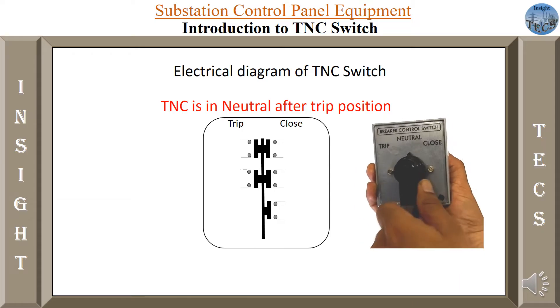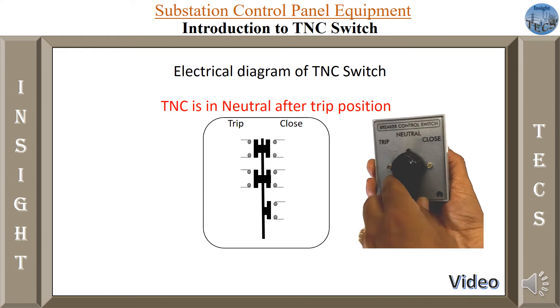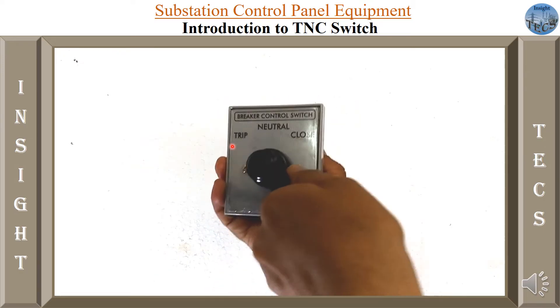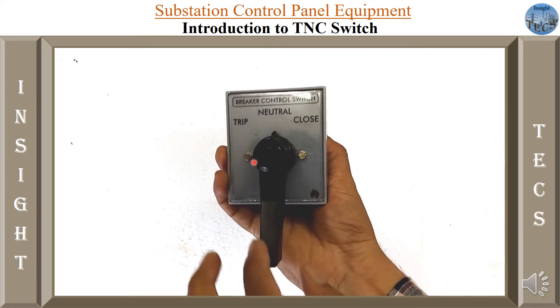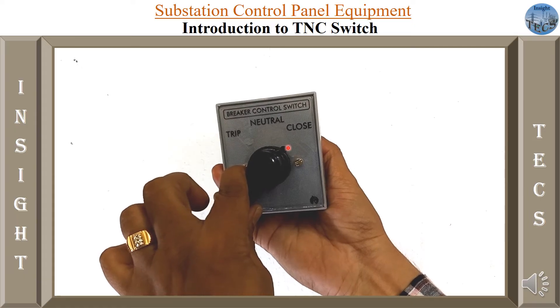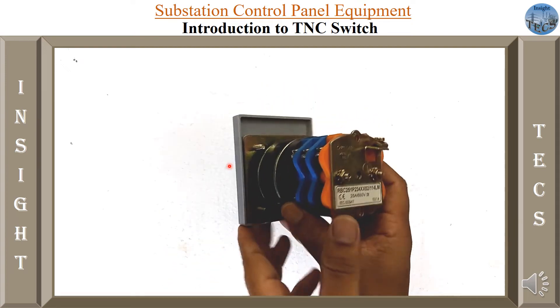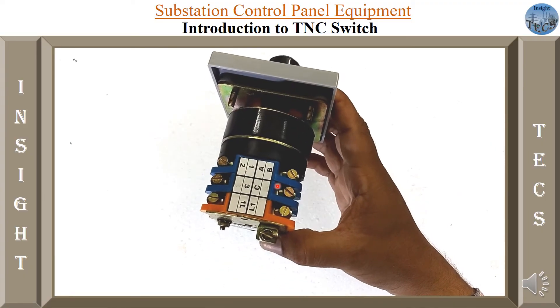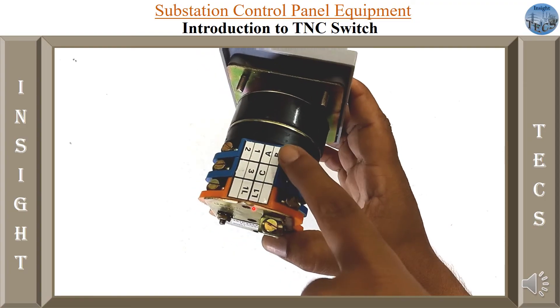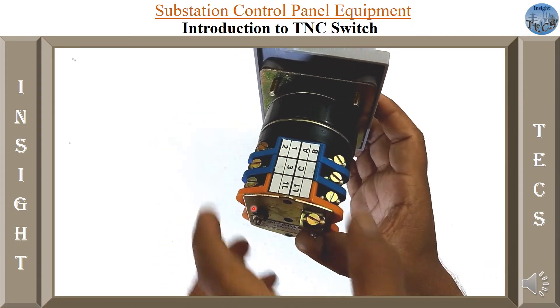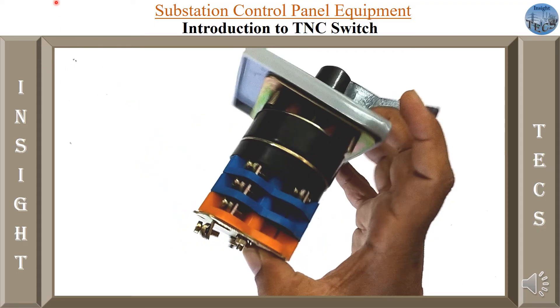Now let us see a video showing how an actual TNC switch is and how it operates. As you can see, this is a trip-neutral-closed switch — a breaker control switch. Using the handle, we can move it towards the trip position, bring it back to neutral, then move it towards the closed position, and it comes back to neutral. Neutral is its normal position. On the back side, you can observe the NO contacts for each of the three positions: trip, neutral, and closed.